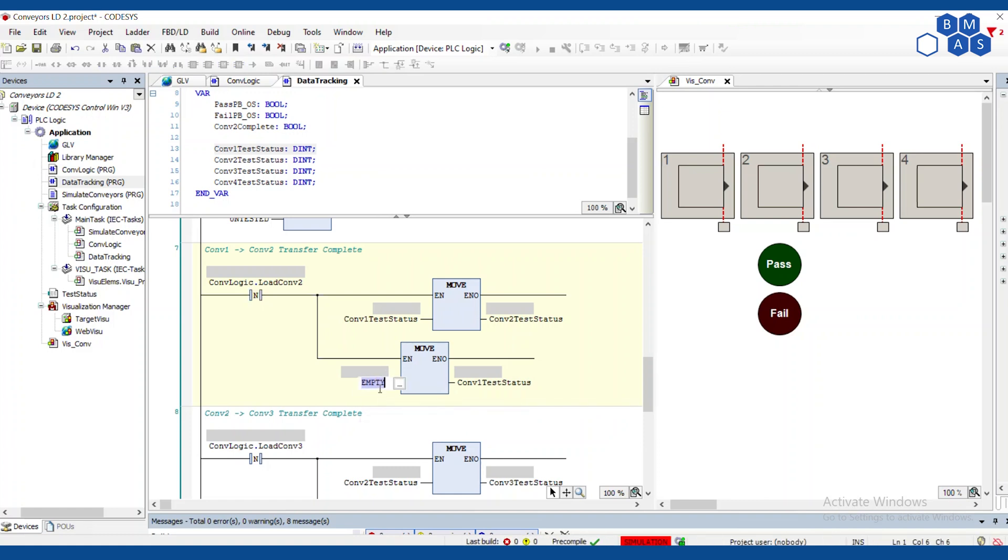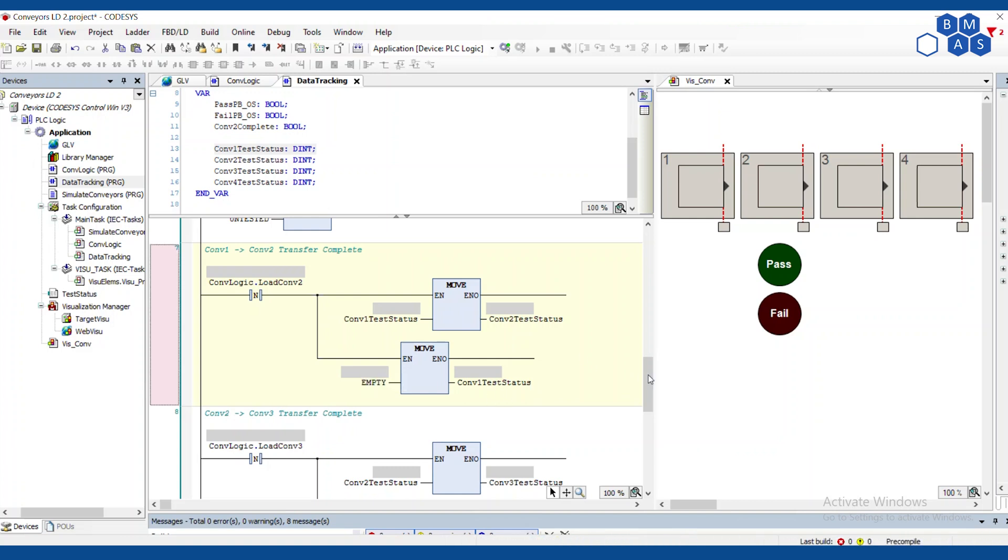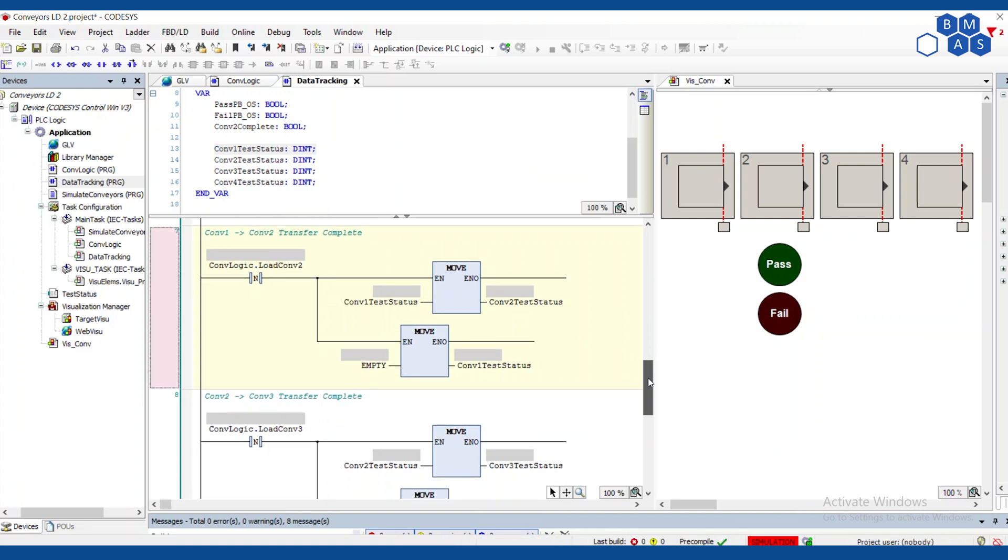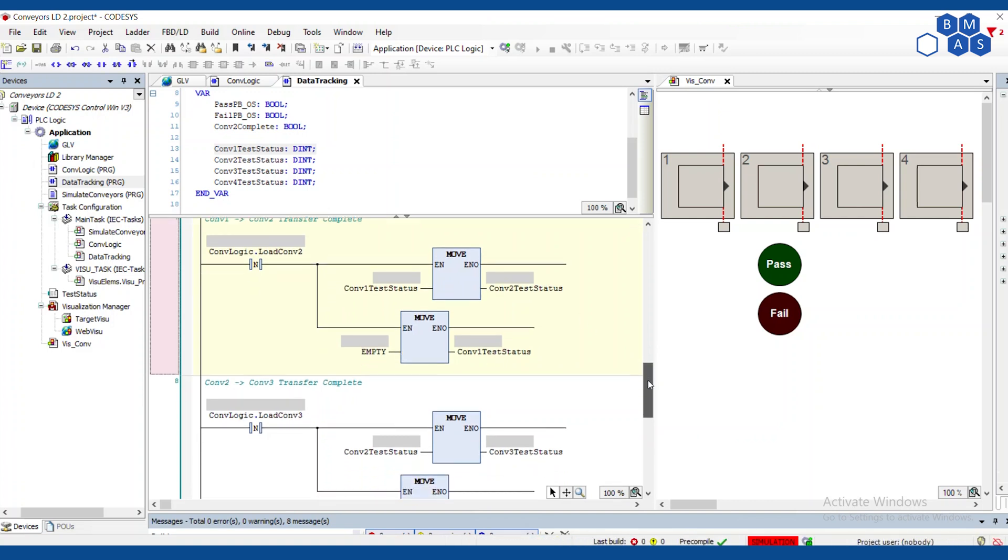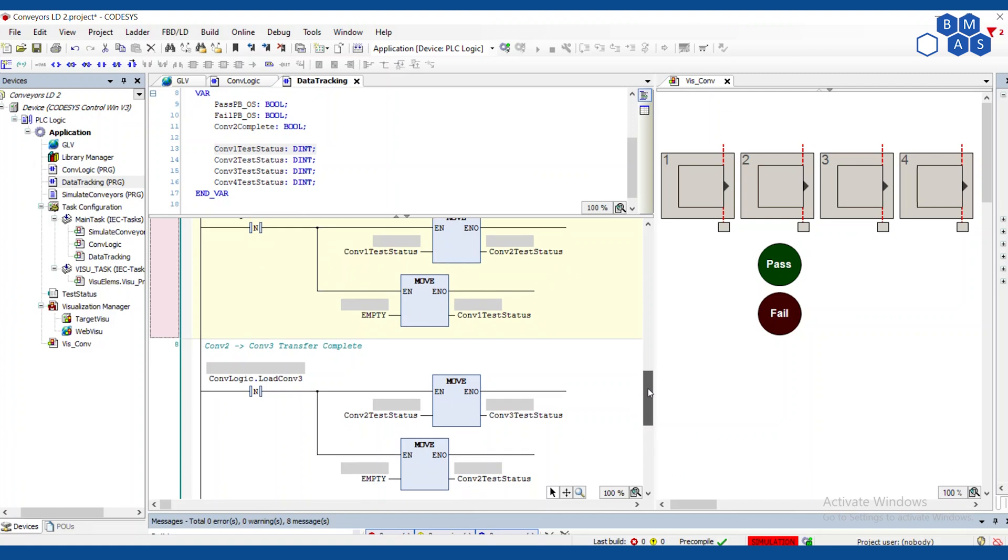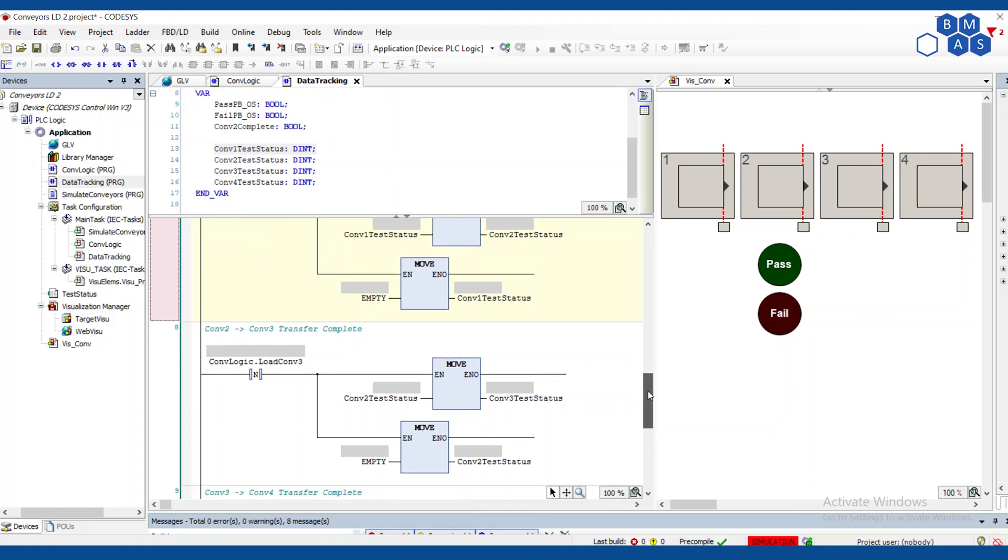So when load conveyor two is done, the falling edge, the negative edge, then we're going to take whatever information was in conveyor one, we're going to put it into conveyor two, and we're going to clear out conveyor one again. In this case, I'm putting that constant empty into conveyor one. And by the way, this having a constant for empty, sometimes for a complicated, complex data type of structure, having a constant isn't always easy in some platforms. So you could just have a tag or a variable that has a bunch of zeros in it.